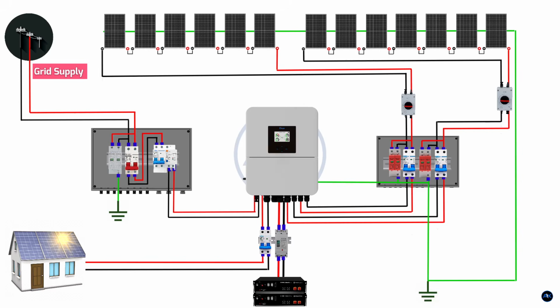Step 6. Monitoring and commissioning. Once all connections are secure and verified, turn on the breakers in the correct sequence. Usually DC first, then AC, then activate the inverter. Most hybrid inverters come with a monitoring app or software. Connect your inverter to your home Wi-Fi or network to track production, consumption, and battery status. Perform initial system checks to ensure everything is operating as expected.